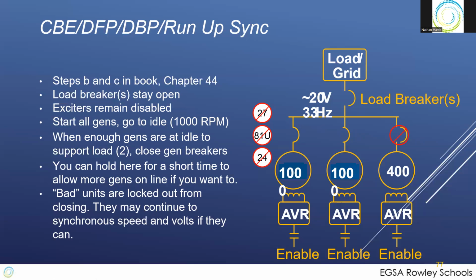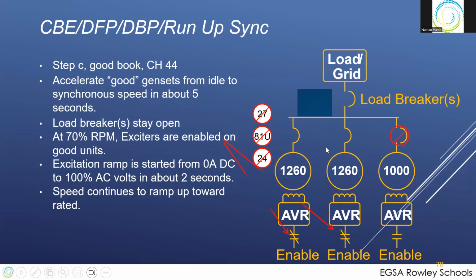You can hold for a little, or you can go ahead and continue. If you continue, you lock out that third unit. But I only need 2, so I'm going. Now I've got my 2 gens and I'm good to go. I'm going to turn on the exciters and let the speed ramp up at about 1260, just above idle, at about 70% RPM. The exciters are enabled.